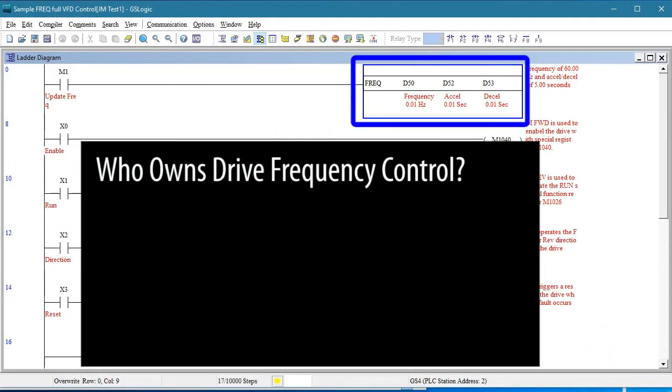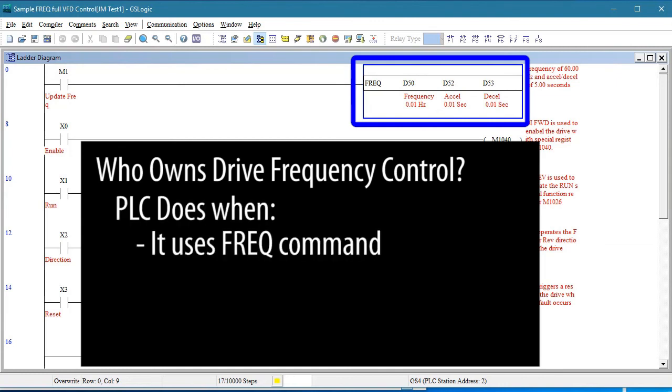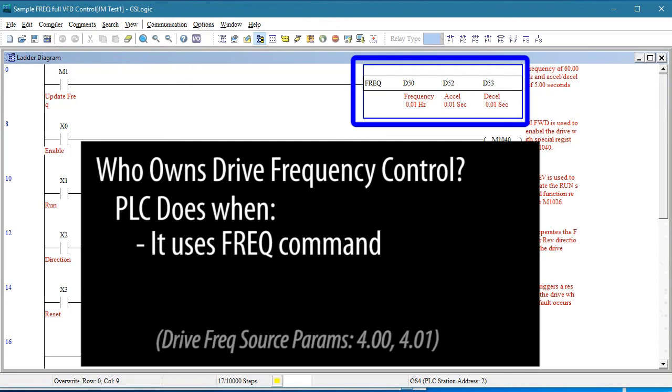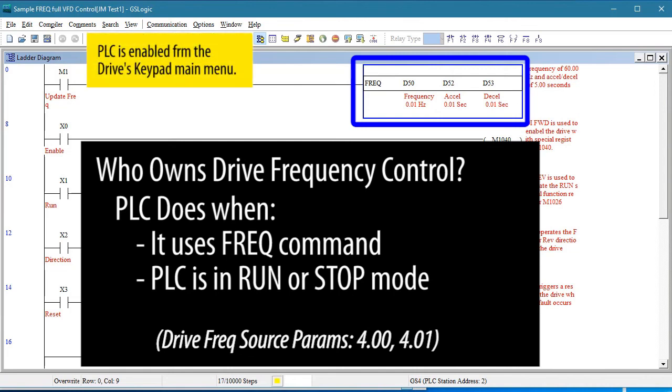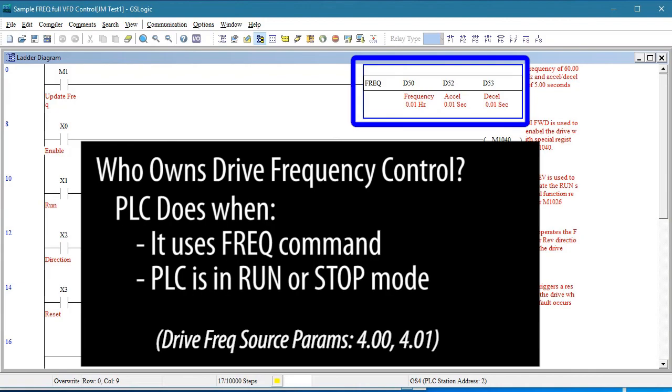When you use the frequency command in your ladder code, that tells the drive that you want the PLC to control the frequency and that it should ignore whatever you told it to do in parameters 4.0 and 4.01 as long as the PLC is enabled. If you disable the PLC, then the drive goes back to being controlled by parameters 4.00 and 4.01.